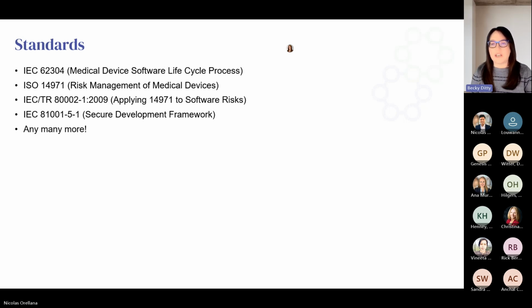And as you go into cybersecurity, you also need to develop a secure development framework within your quality system for your software and your medical device. And IEC 81001-5-1 will help you with that. Now, in the world of cybersecurity and medical devices, there are a lot of new standards constantly being released. There is not one definitive go-to standard for that. However, IEC 81001-5-1 is becoming recognized worldwide, and other regulatory bodies are requiring compliance to that standard. So it will be helpful for you to get familiar with that standard.